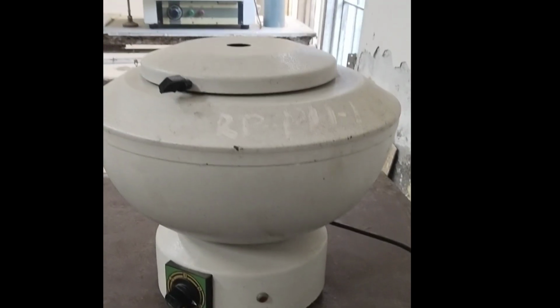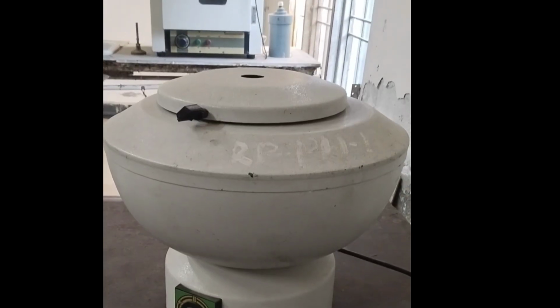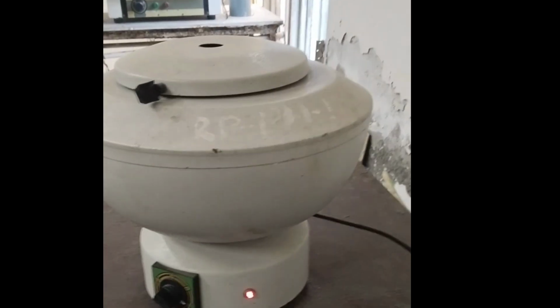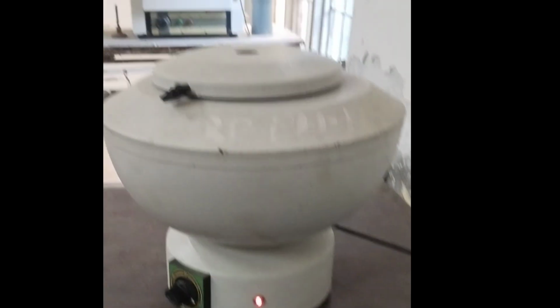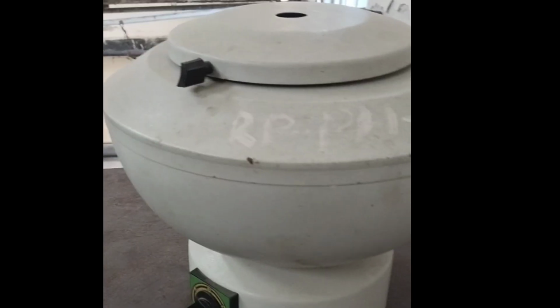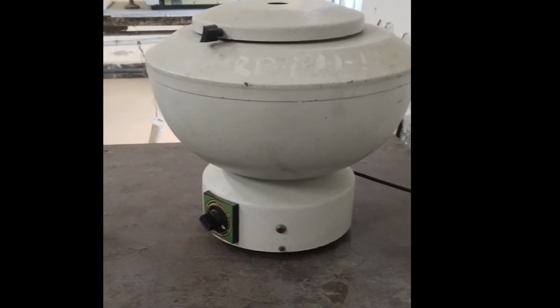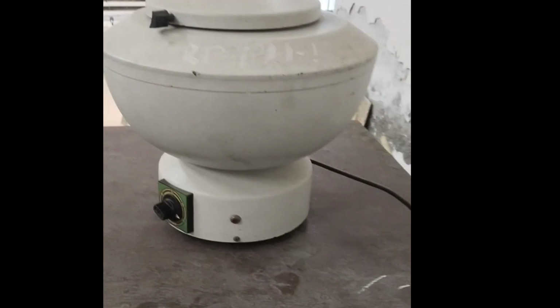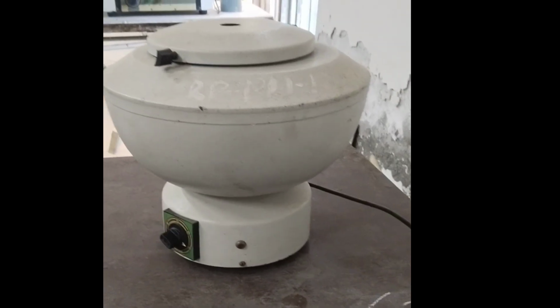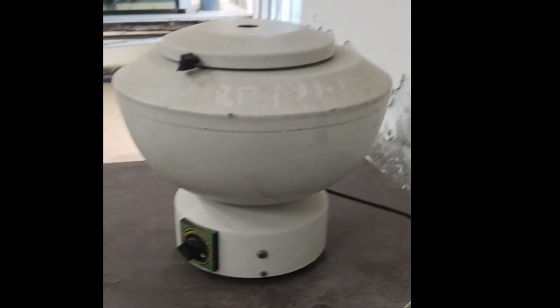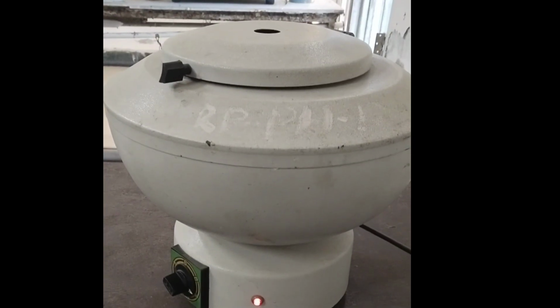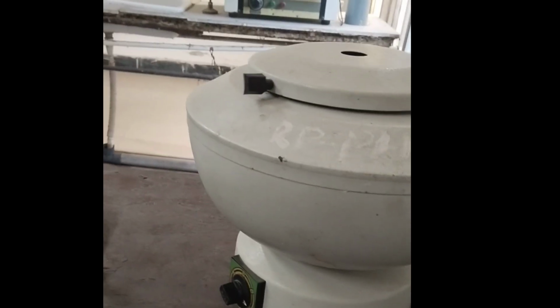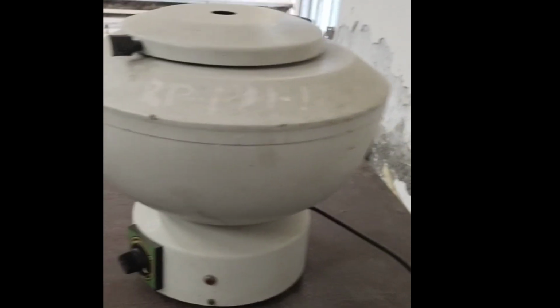How to operate a centrifuge? Place the centrifuge in the operating place, preferably a very stable lab workbench. Open the centrifuge lid. Keep the power off for now. Perform basic cleanup as per the manufacturer's instructions. Put your liquid in the centrifuge tube and insert the tube in the bore holes on the platform. If you have fewer tubes than there are holes, try to distribute them evenly around the platform so that the spin can stay even.